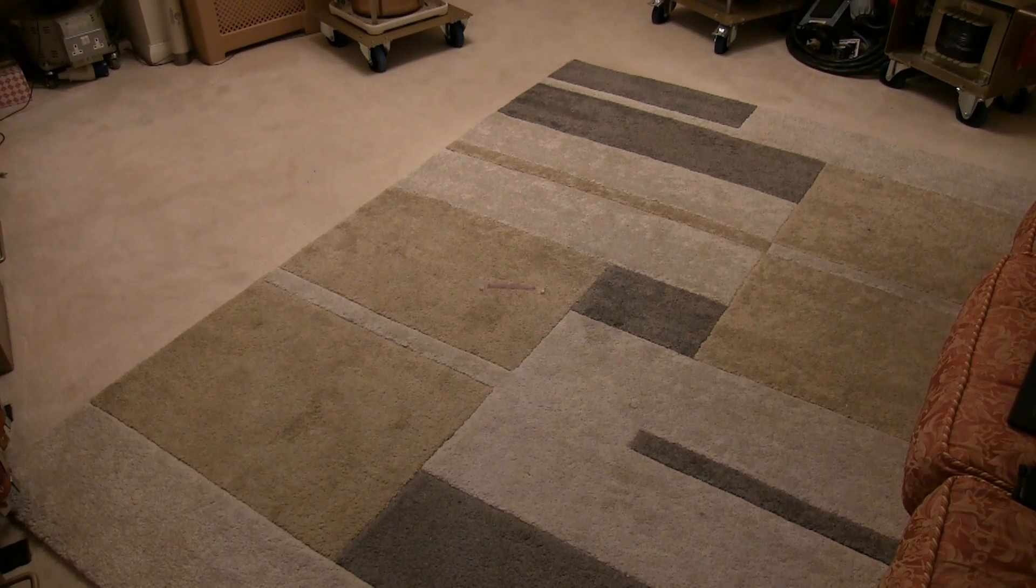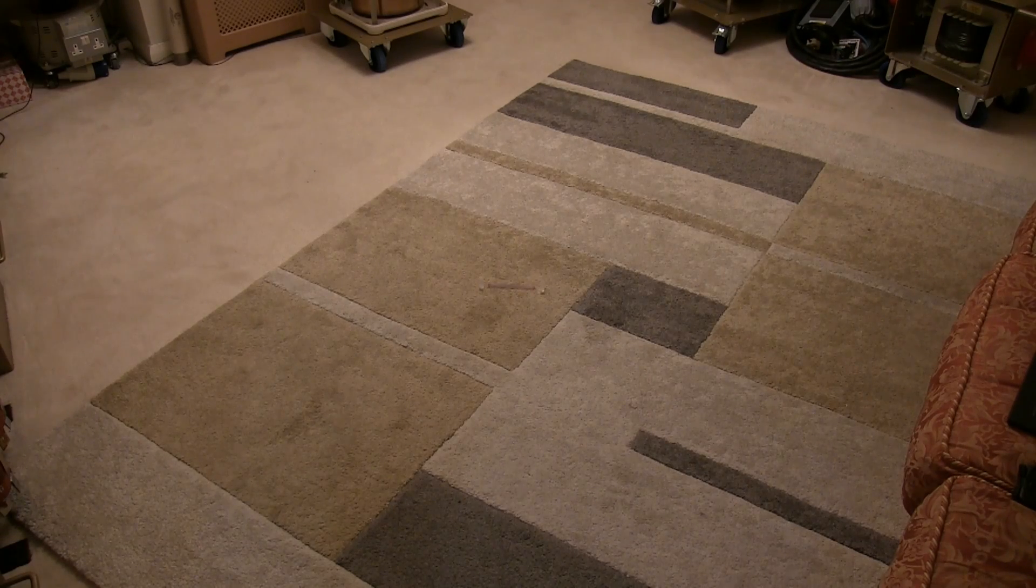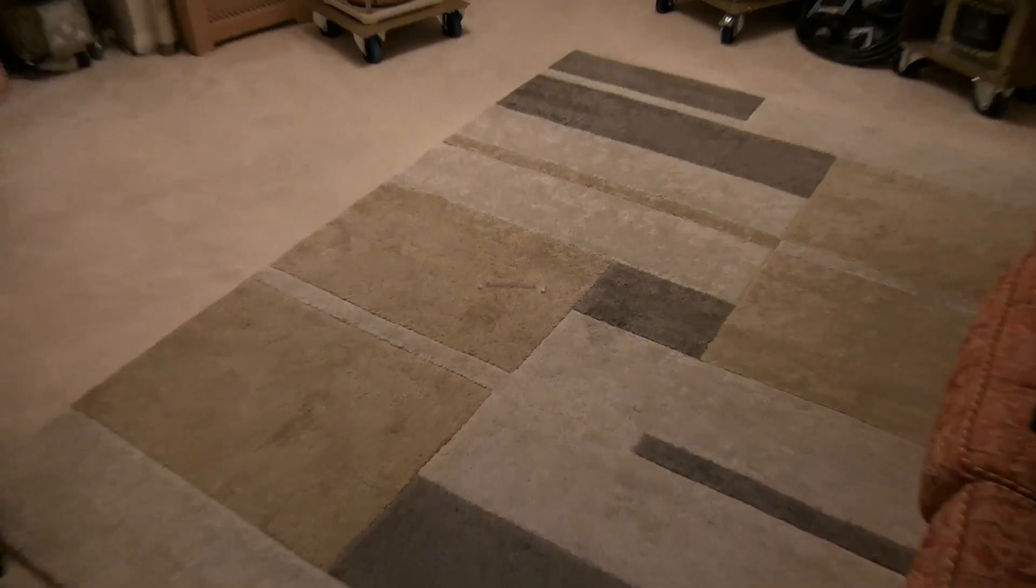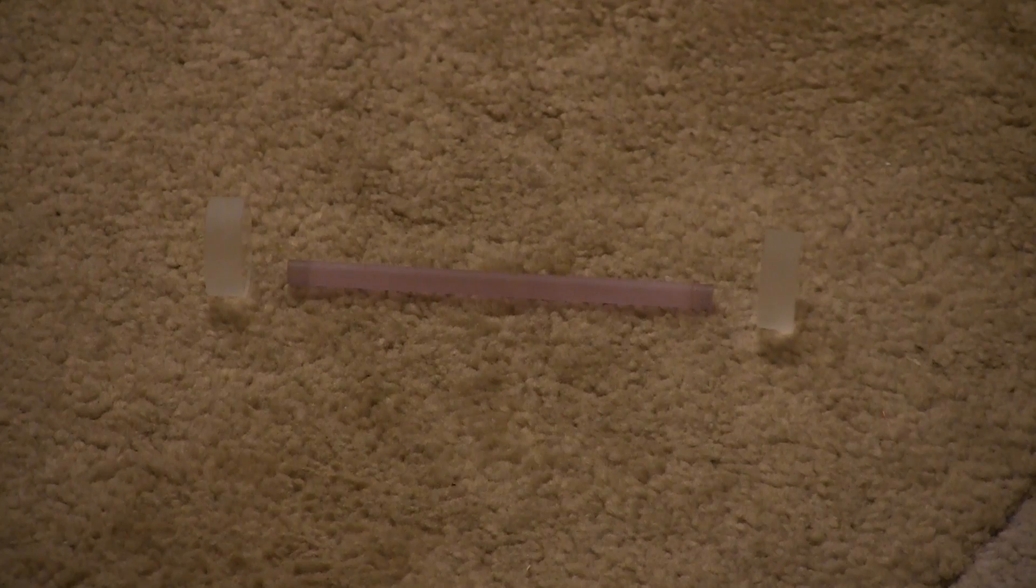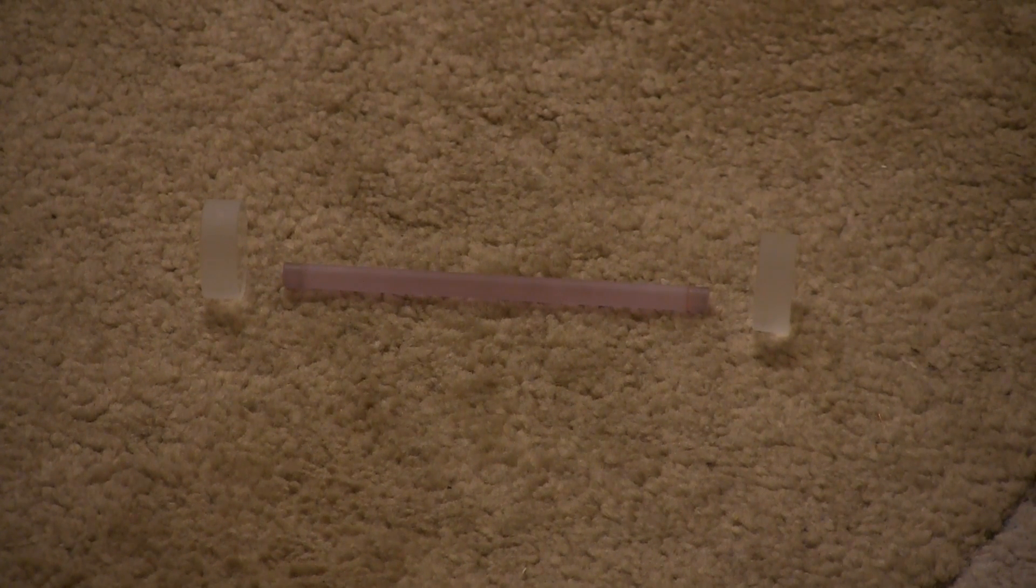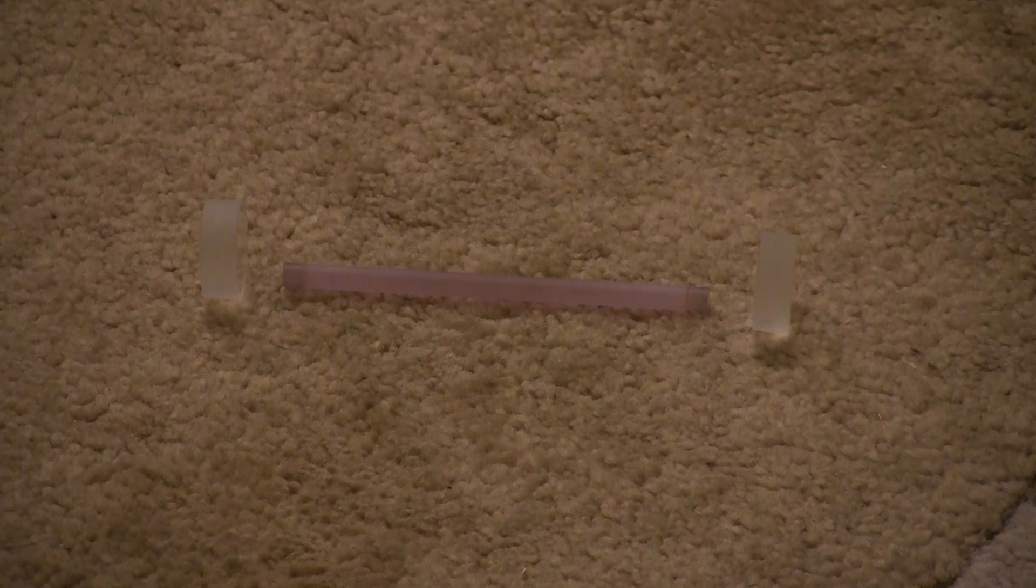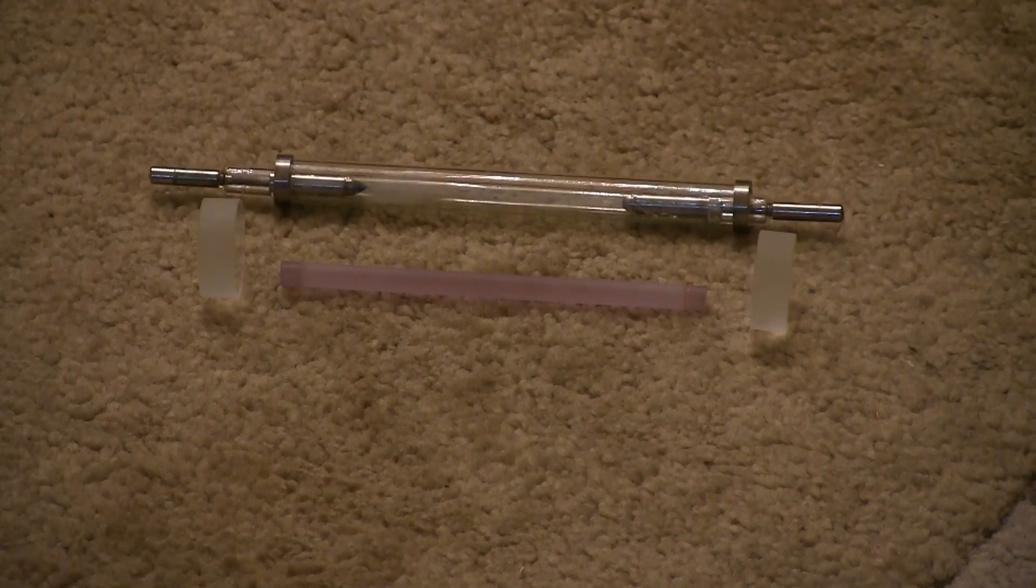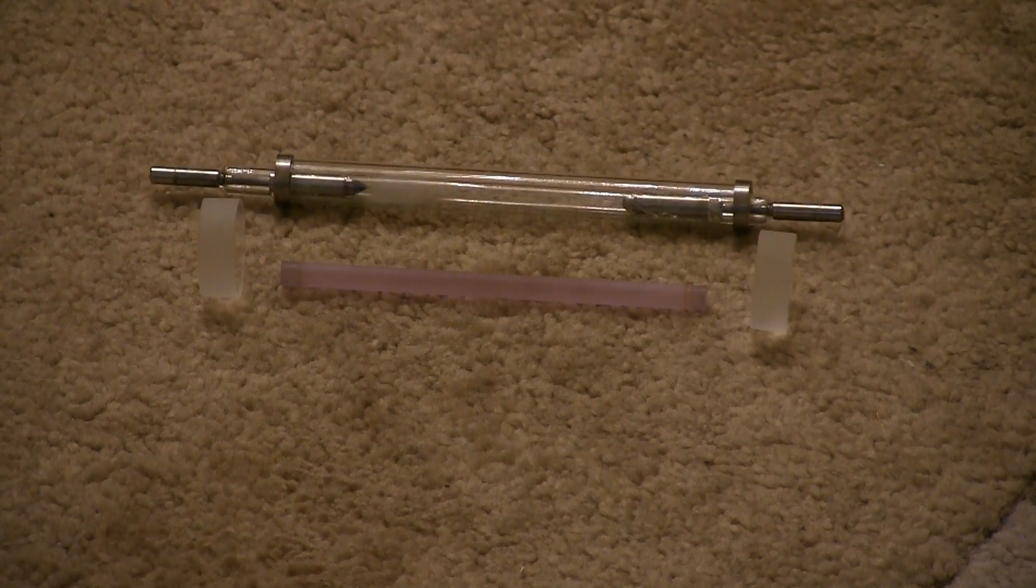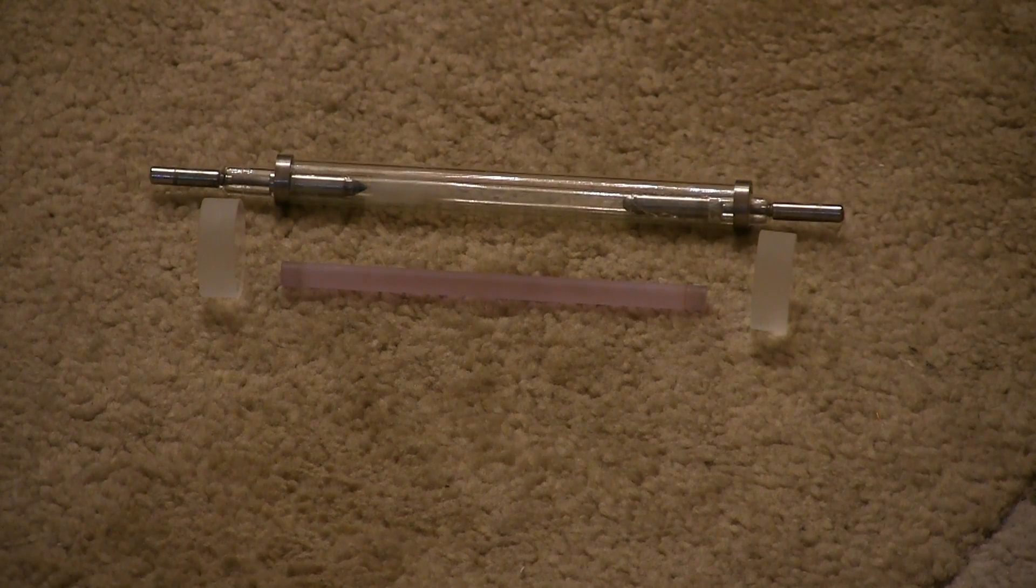So the key component of the YAG laser is right there before your eyes and it's simply that. That's all it is. Two mirrors and an ND-YAG rod. Oh, and you might need a light bulb as well. Now we can see the xenon lamp in the water cooling jacket which pumps that rod full of photons.